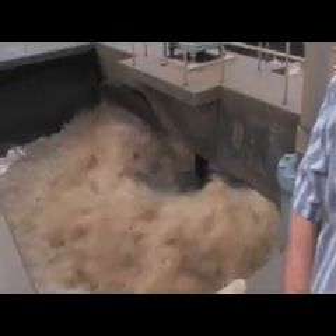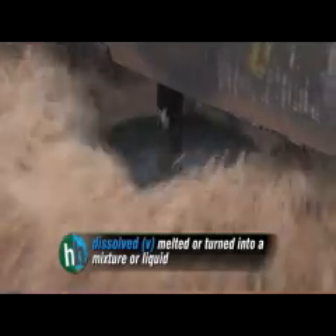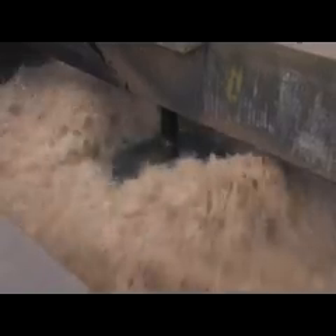The water in the settling tanks drains off the top and flows through to the next stop. Once the water leaves the primary settling tank, it comes into this aeration tank, where these mixers are putting dissolved oxygen into the water. There are little bugs or organisms naturally in the water, and they help clean it by eating the sewage. Just as fish need dissolved oxygen to breathe, these bugs need dissolved oxygen to eat up all the organics in this wastewater.